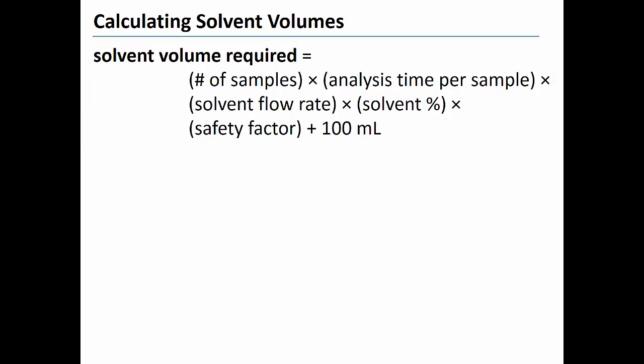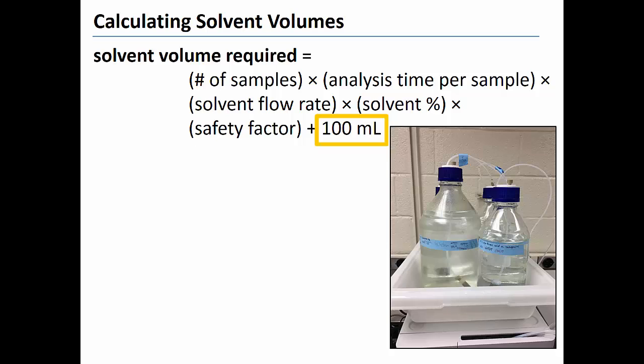You should use this equation to obtain a conservative estimate of the amount of solvent needed to analyze a batch of samples. I recommend a safety factor of 1.2 which corresponds to a 20% excess. This excess accounts for the fact that the pumps are pumping mobile phase in between each sample as well as during the analysis of each sample. I also recommend that you add 100 milliliters of extra solvent to ensure that the solvent levels never fall below the height of the inlet tubes.